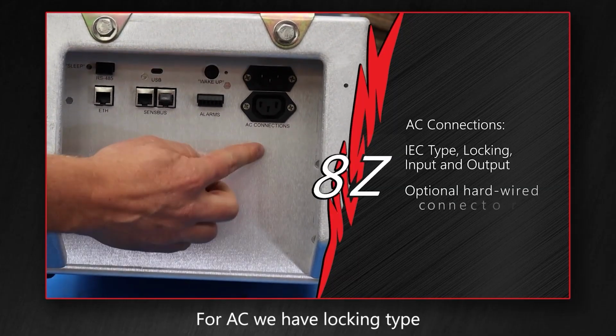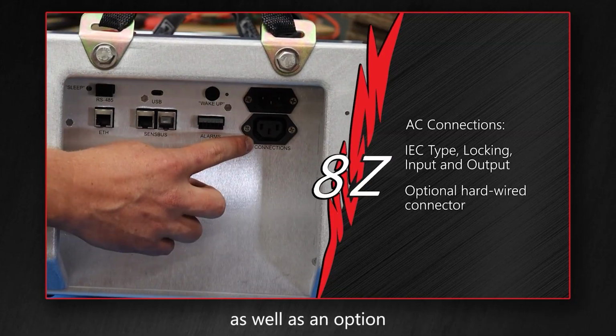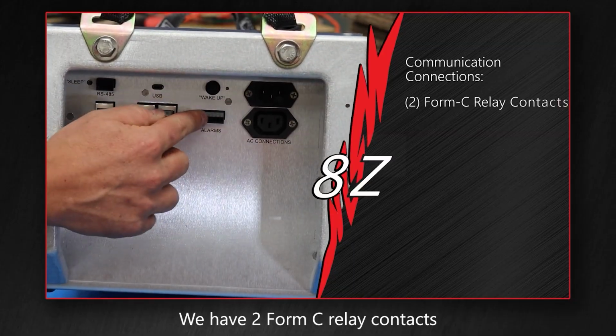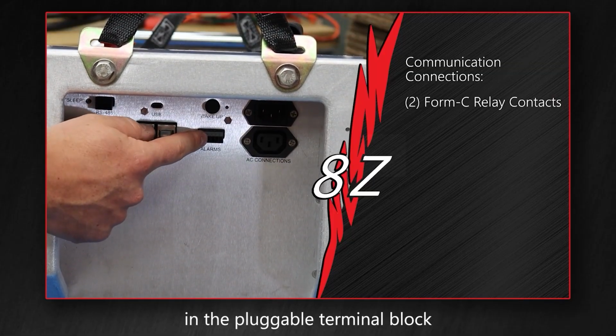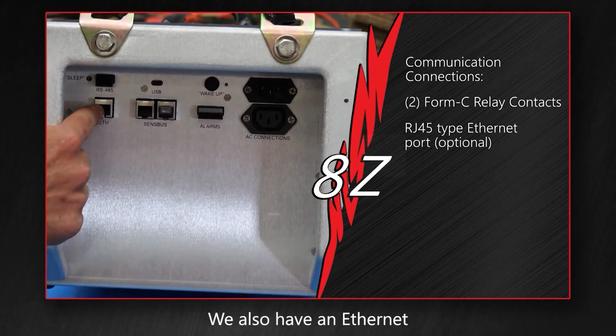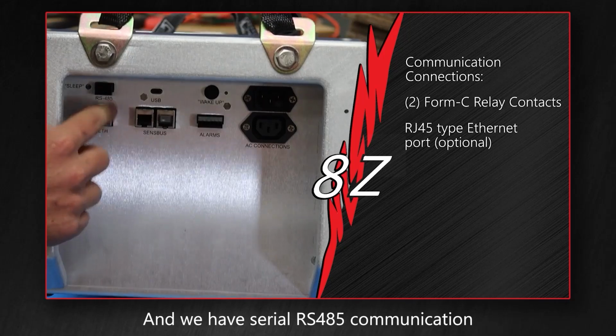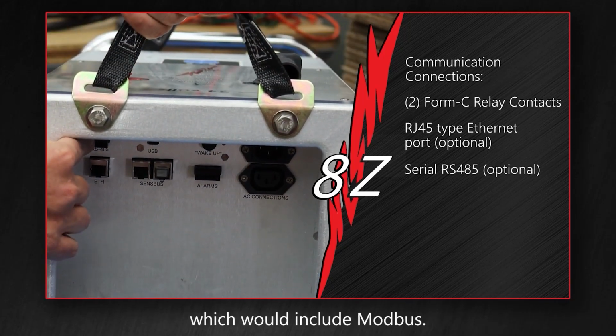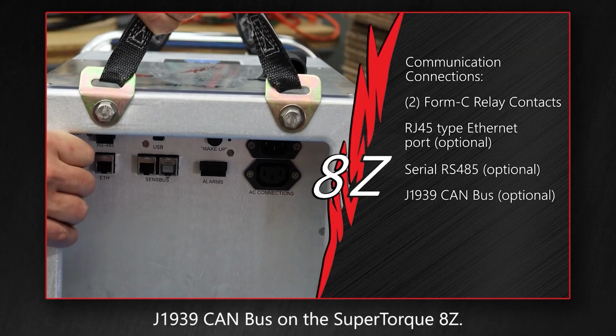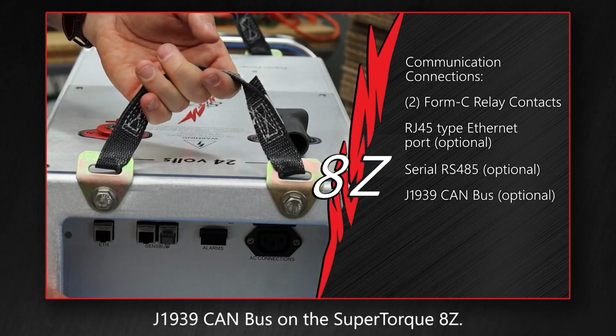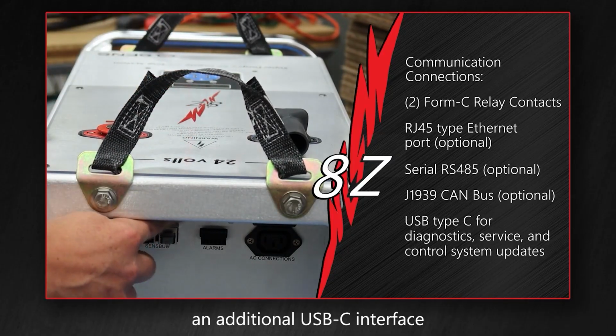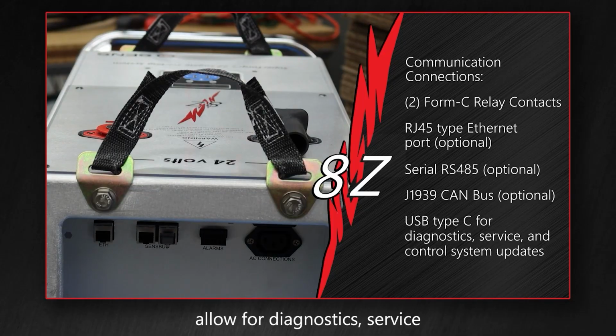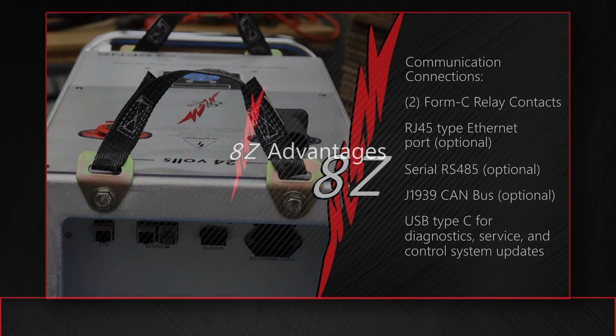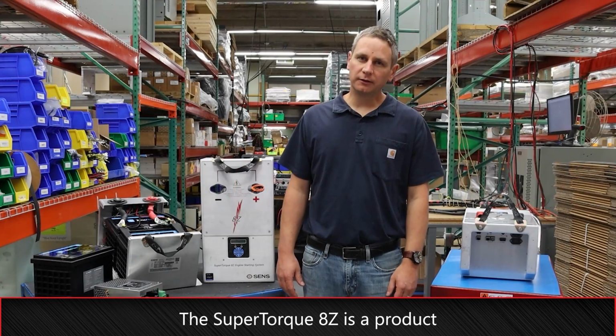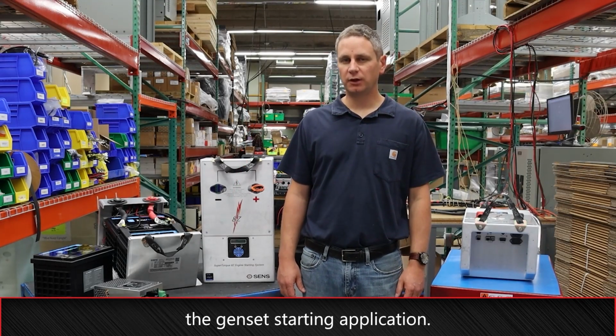For AC, we have locking type IEC connectors, as well as an option for hardwired input. We have 2 Form C relay contacts and a pluggable terminal block for communication. We also have an Ethernet port, RJ45 type, and we have serial RS485 communications, which would include Modbus. And we also support J1939 CAN bus on the SuperTorque 8Z. There's also an additional USB-C interface, which will allow for diagnostics, service, and field updates for the SuperTorque 8Z control system. The SuperTorque 8Z is a product that really revolutionizes the genset starting application.